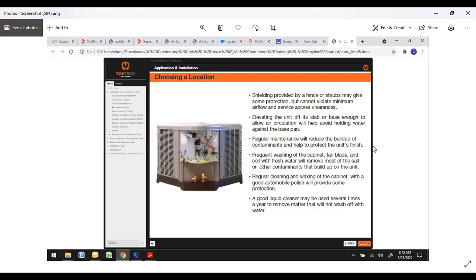Regular maintenance will reduce the buildup of contaminants and help protect the unit's finish. We don't really have coastal issues here, but a good coat of wax, as you dry wax, will keep that cabinet looking clean and not faded. Frequent washing of the cabinet, fan blade, and coil with fresh water will remove most of the salt. We don't have salt here, but other contaminants could build up. They do recommend a regular cleaning and waxing. The finish will fade over time. It's a guarantee. It starts to look old, so a decent wax job once a year on maintenance is not a bad idea, and it's a good selling point for your maintenance.